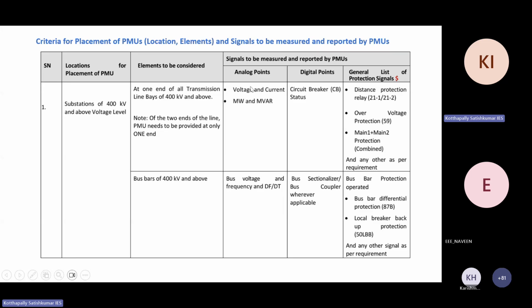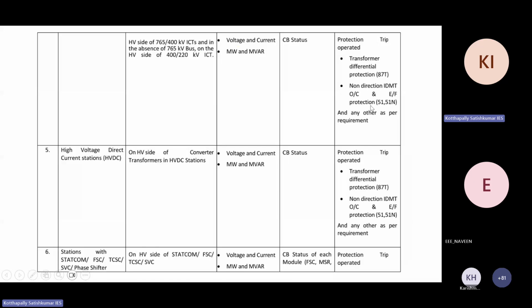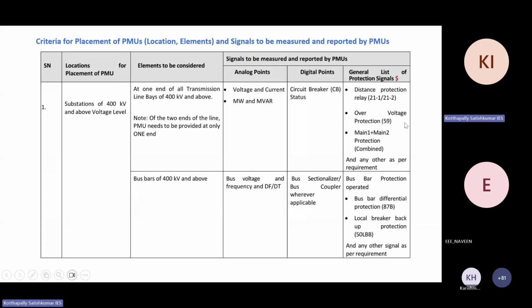So these are the criteria for PMU location. You can get this from our reports, CEA reports also. I will briefly explain a few things. For example, for substations of 400 kV and above voltage, at one end of all transmission lines you should have one PMU. For example, if you take a 400 kV transmission line from Ramagundam to Hyderabad, you have the option to place one PMU at Ramagundam, or you can place a PMU at Hyderabad. But each 400 kV line should have one PMU at either end; it is not compulsory at both ends, only on one side of the 400 kV line. But we also made one more condition. For example, if it is an inter-regional line, then in that case the PMU should be on both sides. What are the analog points? Voltage and currents. Digital points are the circuit breaker. And the PMU also takes data from the protection signals.